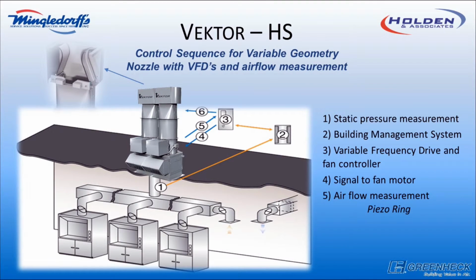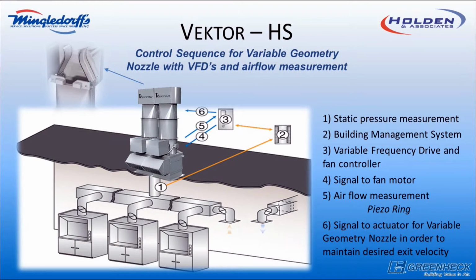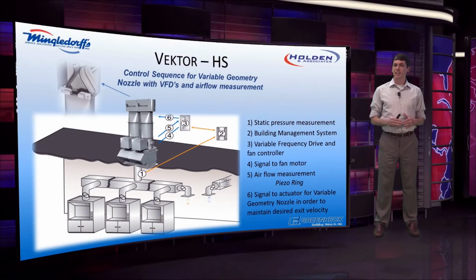From this, the airflow ring will tell the controller to signal to the blades and the actuators what needs to take place. So as the piezo ring is telling the controller where we are in terms of airflow, a corresponding nozzle position is occurring. It'll open and close based on the demand in the space. Again, the benefits of this system is saving fan energy without having to use a bypass air damper for variable volume application.